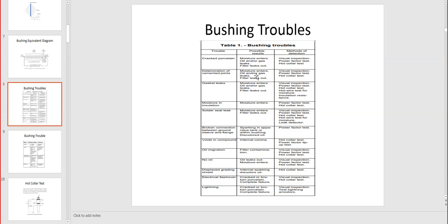Bushing is number 3 in the total, so windings will be number 1 in the root cause of transformer failure. Number 2 will be the oil that is contaminated, and number 3 is the bushing, followed by number 4, the tap changer, especially if it's a load tap changer. So those will be the 4 main root causes of transformer failure. Different percentages are given by CIGRE or IEEE, close to each other but not exactly the same. You're going to see they differ in opinion a little bit on different things.